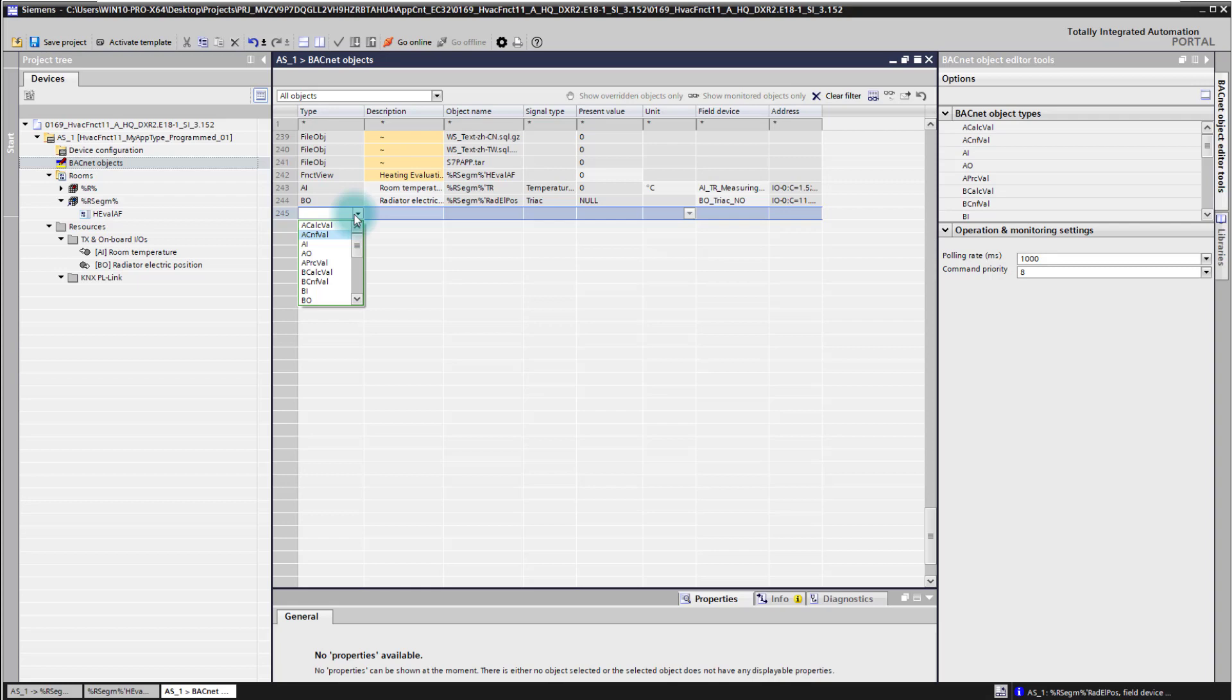But let's finalize the group of our value objects. The last one is the process value and the process value gives you the opportunity in your CFC code to create an object which can be then also overridden by the system. So that's the three main objects we are using for creating CFC code.